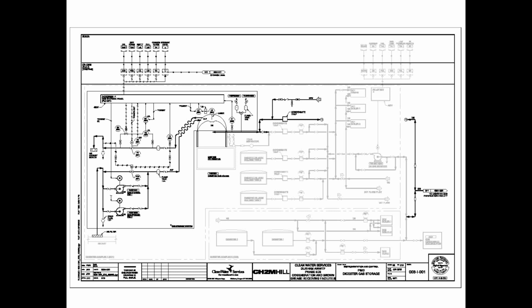And then below is what's actually out there in the field. You can actually see pumps, tanks, and there are flow meters and valves that are located down there. And so the more you look at these and the more you can trace out what's going on, the better off you are. Normally, when you read a P and ID, you read it from left to right and from up to down. You can start tracing things out until you get all the way to the right-hand side, and then there's an arrow and a tag, and that refers you to another drawing, so you can go to another drawing if you need to and trace that out and find out where the information is going from there.